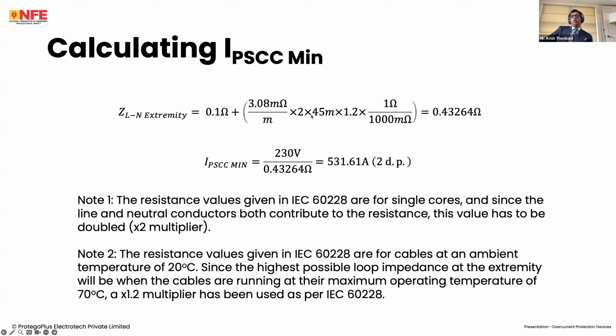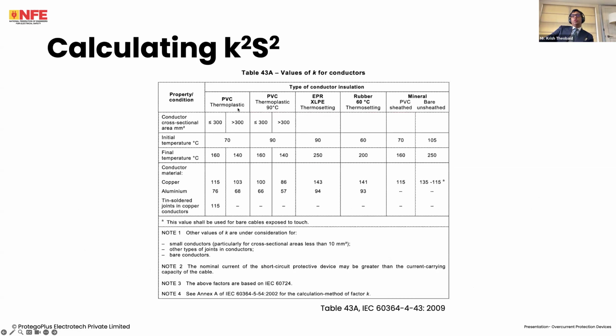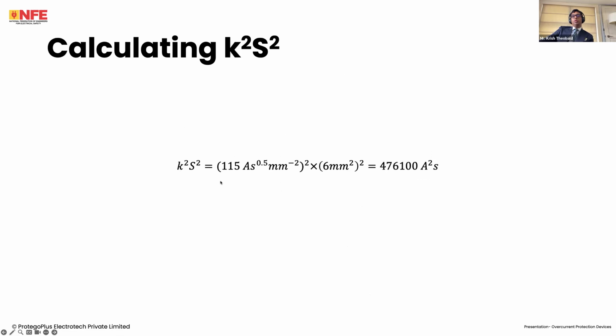This is just an explanation for this. Resistance values are for single core cables, and since the line and neutral conductors both contribute to the resistance, this value has to be multiplied by 2. The resistances are given at an ambient temperature of 20 degrees, but the highest possible loop impedance at the extremity is when the cable is operating at maximum operating temperature, so 1.2 is taken into account. This is simple. What value of K do I choose? PVC cable, less than 300 square mm, 115 is the value I choose.